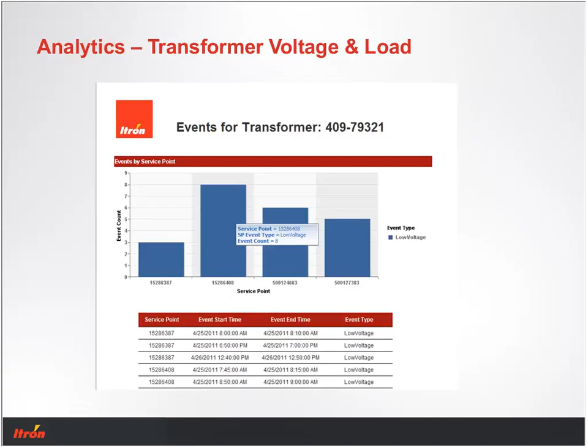And here I can see that actually there were events, low voltage events, on all 4 services that were on that transformer. And you can see the listing of the events down below. So that tells me that, okay, it certainly is that transformer with loads. Maybe I should look at the individual loads rather than the aggregate. So now we take a look at a graph that shows each one of the individual service points and also shows the voltages for each one of those.